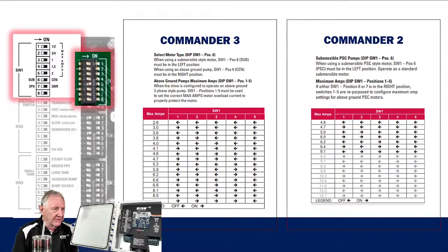But with a centrifugal motor, we're going to set this drive up based on max amps, not horsepower. And that's the case for either both the Commander 3 or the Commander 2. So again, that top bank up there, it's very, very simple to understand as you look at it. It's very well labeled, and all you're doing is basically letting the drive know what type of pump motor it's going to be operating.